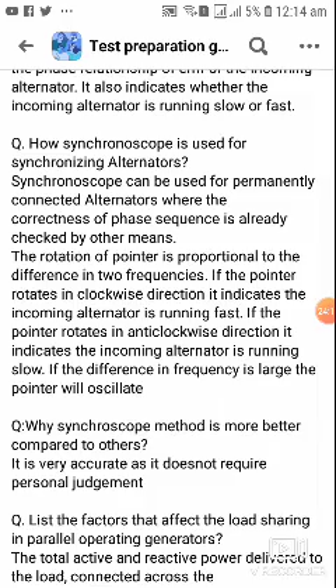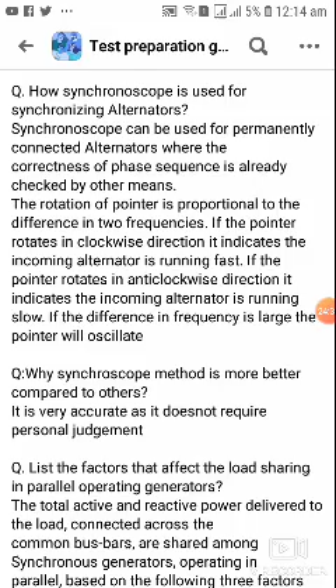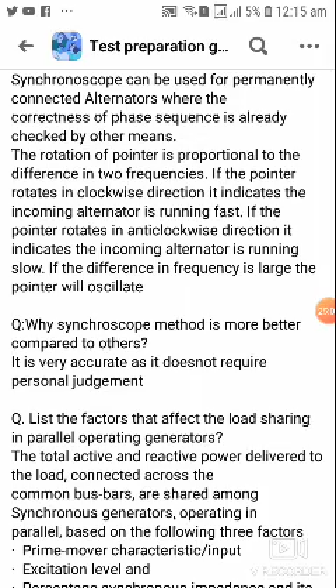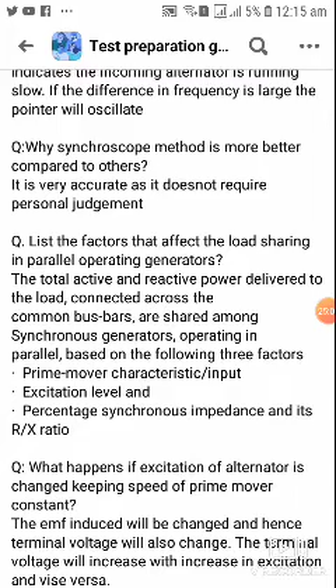Question number 45. How is synchronoscope used for synchronizing alternators? Synchronoscope can be used for permanently connected alternators where the correctness of phase sequence is already checked by other means. The rotation of the pointer is proportional to the difference in two frequencies. If the pointer rotates in clockwise direction, it indicates the incoming alternator is running fast. If the pointer rotates in anti-clockwise direction, it indicates the incoming alternator is running slow. If the difference in frequency is large, the pointer will oscillate.